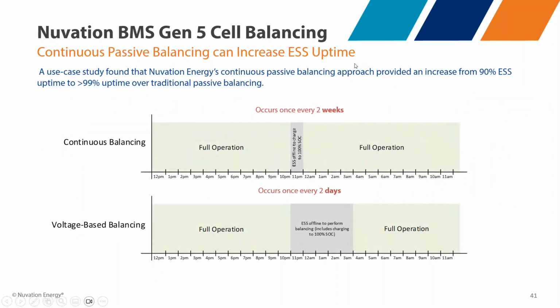So to compare what this looks like and the impact on uptime, if you have a continuous balancing system, you only need to go to a high state of charge every couple weeks in order to capture data as to where the system is at. This is because cells age pretty slowly. Batteries don't change a lot cycle to cycle. They do age over time, but it's a fairly small change per cycle. And so the same cells that have a lower individual state of health or usable energy will stay the same largely cycle to cycle. So you don't need to update your snapshot every day.